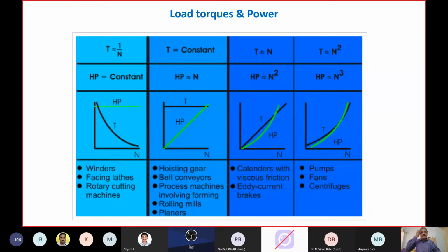This slide will explain to you the 4 different torque characteristics of the load. This is not that of the motor. The motor's whole-time job is to deliver what the load demands. But we have to understand what the characteristics of the load are. This one first is torque inversely proportional to speed, where the power will remain constant, HP. This is an American slide, therefore HP. You can read it as kilowatt. The torque will reduce as the speed increases. This is the x-axis for speed.